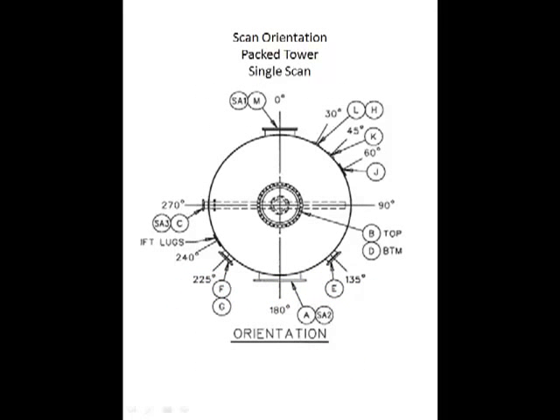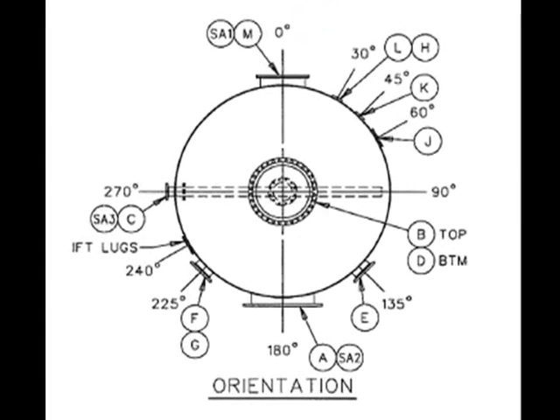This is an example of a gamma scan of a packed tower where the results indicated that fouling was present. Because fouling was suspected, a single scan of the tower was performed rather than a full grid scan.